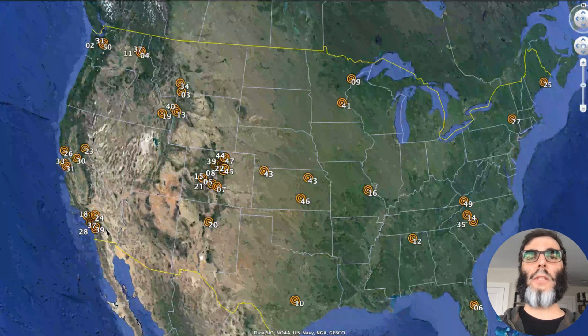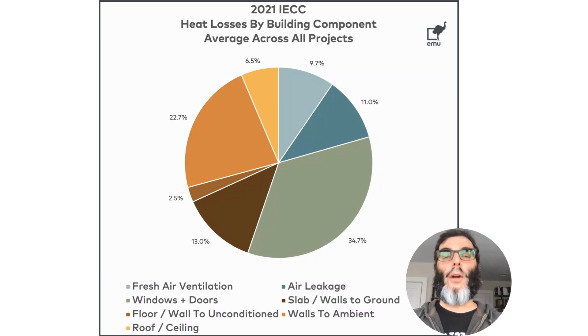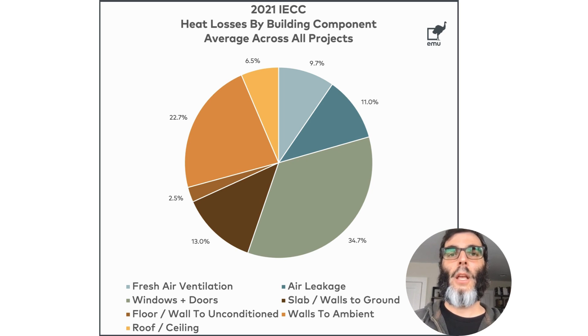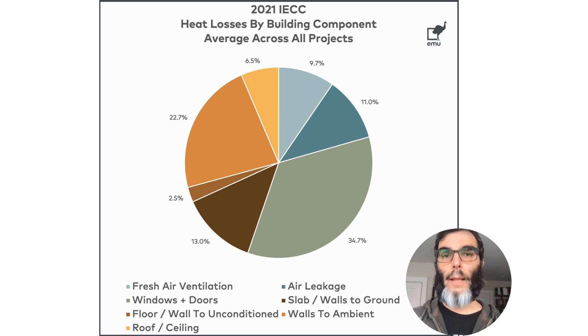These are the 50 projects that we analyzed in our report, and this is where we found the breakdown of the heat losses. If you look at this chart, the number one cause of heat loss in homes is through the windows. Second is exterior walls. Third is heat losses through the ground to the outside air. And only in fourth place is actual air leakage, which is getting a lot of press these days on the internet.